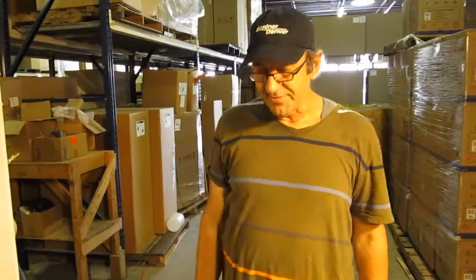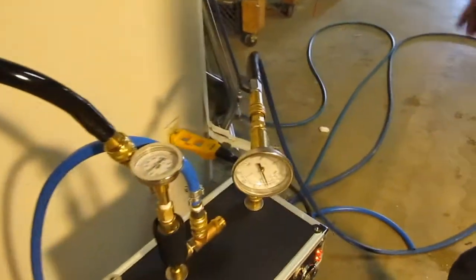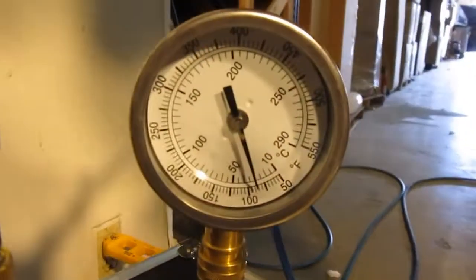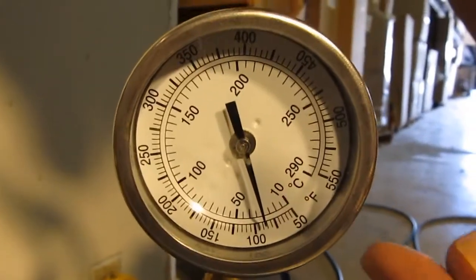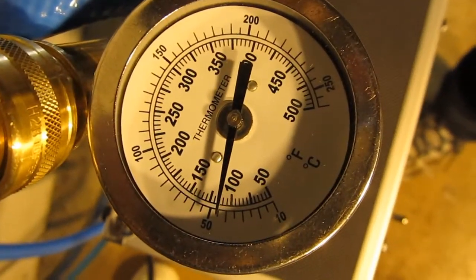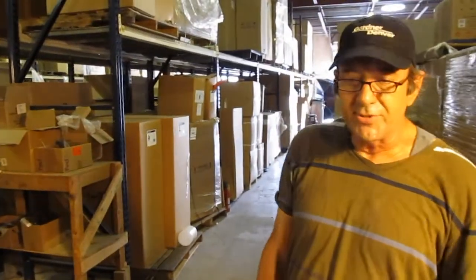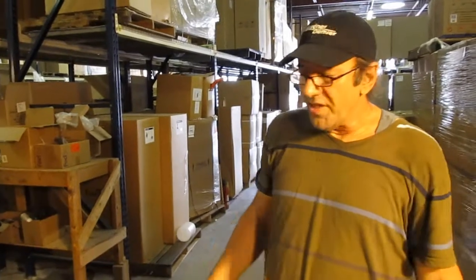It's been about five minutes. What we noticed was the incoming temperature we were measuring, the 90 degrees was the temperature in the hose. Because we're now at 75, 85, about 87 degrees incoming water temperature. And this is with constant flow through a number two tip. We're at 112 and a half. So we're at a 25 degree temperature increase if you're cleaning with a double jet wand with number one tips without ever letting go of the handle.